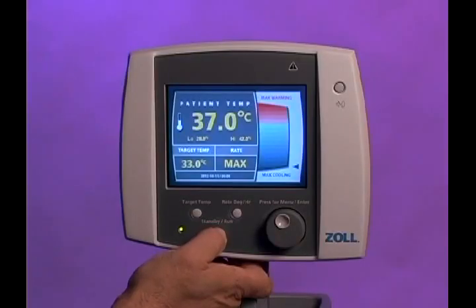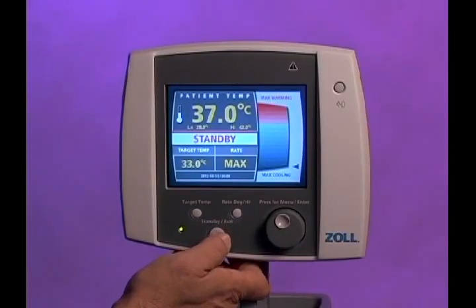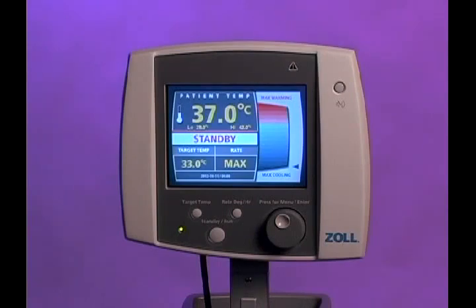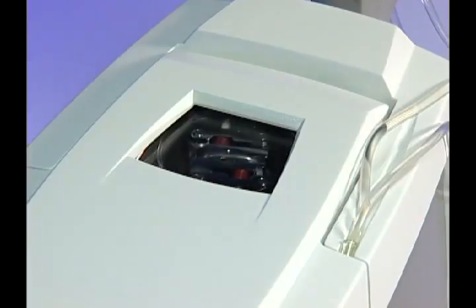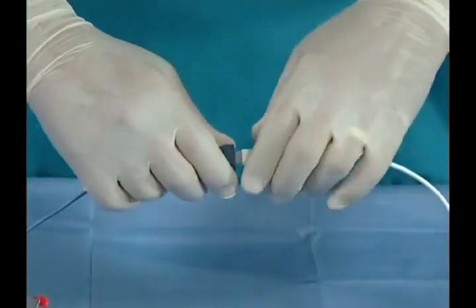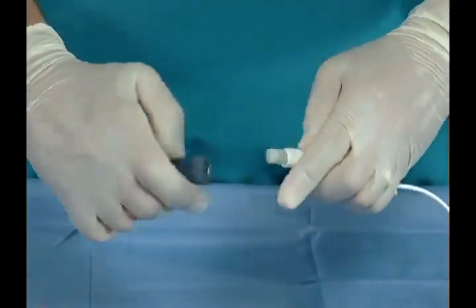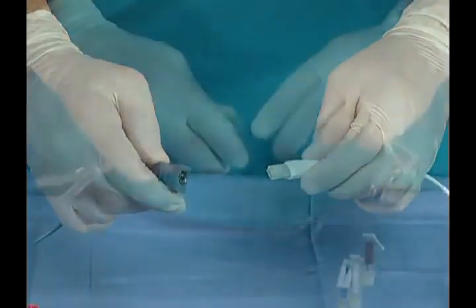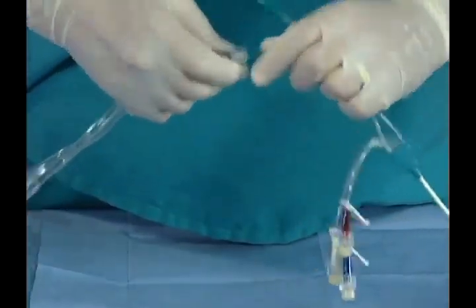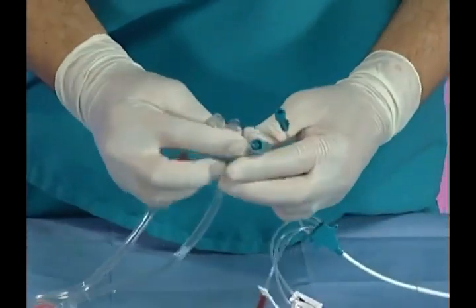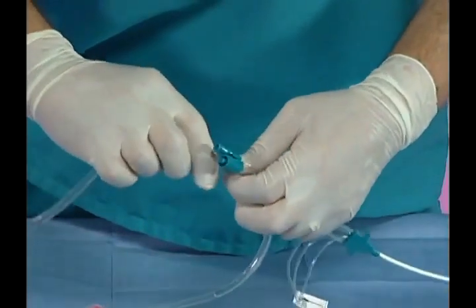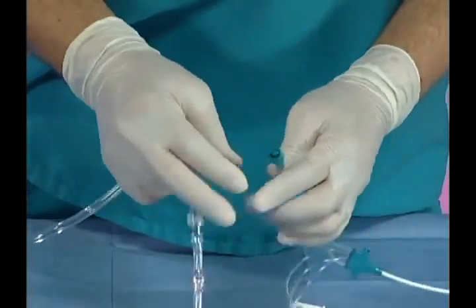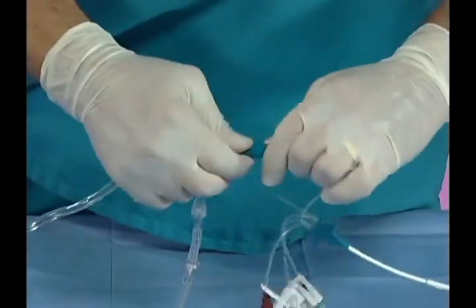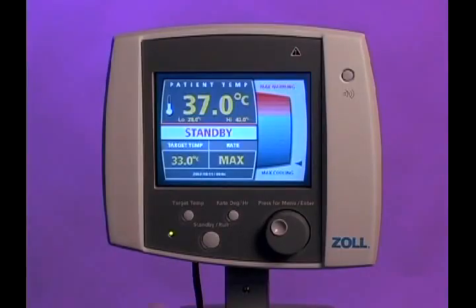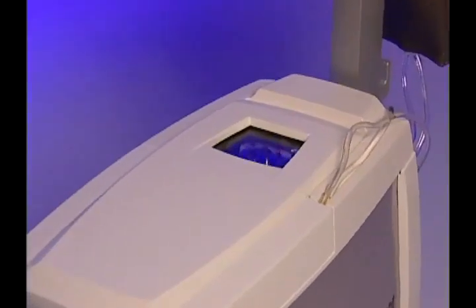Should you need to temporarily disconnect from the patient, first press the Standby Run button to place the system in standby mode. Then, disconnect the temperature probes from their cables. Leave the blue cables with the system. Using aseptic technique, disconnect the saline lines from the catheter and cap all lines or connect them to each other. To reconnect the patient, simply reverse this procedure and press the Standby Run button to resume treatment.